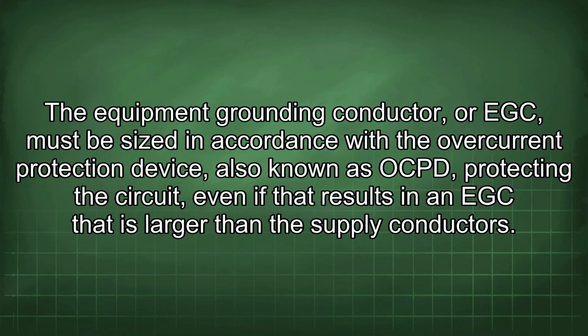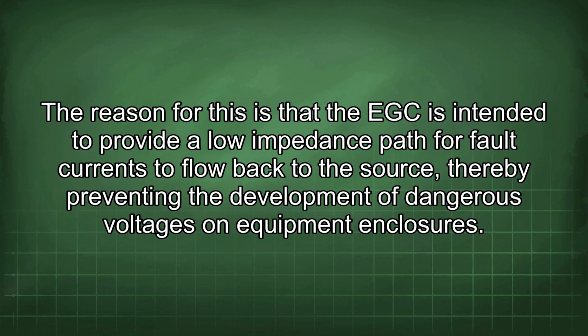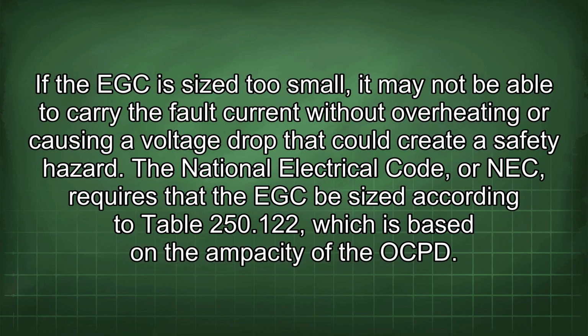The equipment grounding conductor, or EGC, must be sized in accordance with the overcurrent protection device, also known as OCPD, protecting the circuit, even if that results in an EGC that is larger than the supply conductors. The reason for this is that the EGC is intended to provide a low impedance path for fault currents to flow back to the source, thereby preventing the development of dangerous voltages on equipment enclosures. If the EGC is sized too small, it may not be able to carry the fault current without overheating or causing a voltage drop that could create a safety hazard.